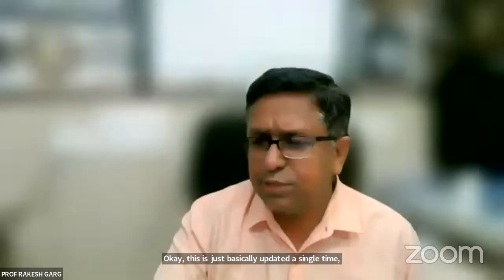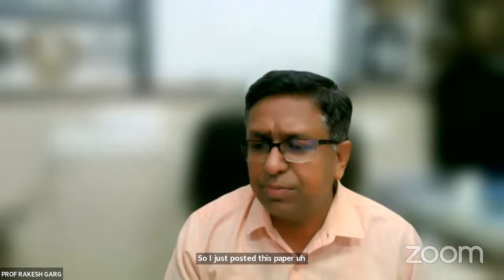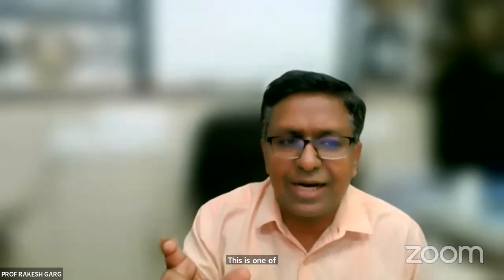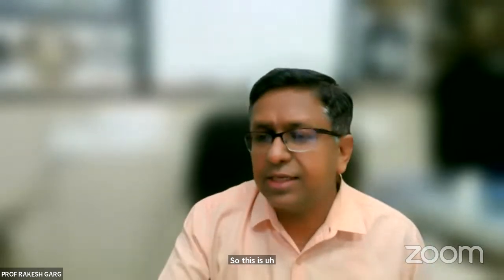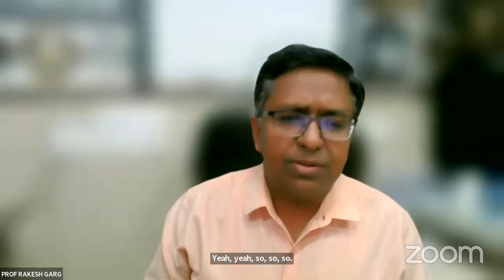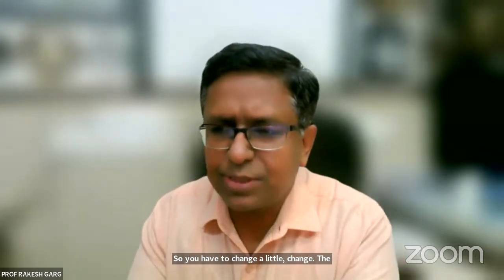You said that two machines' pads can be applied at a single time on a patient's chest. How can these chest pads be applied at a single time, sir? So I just posted this paper onto your YouTube. I'm just posting the link also. This is one of the papers which has nicely been published. So there are two separate sets of pads that are attached here. I will share the picture also in the chat itself. My question is how the pads can be applied at a single time, because there is a right side pad, a left side pad. So you have to change the position a little bit. It can have a little difference of some space in between. Then the sensor will catch up, identifying whether the shock is required or not required.